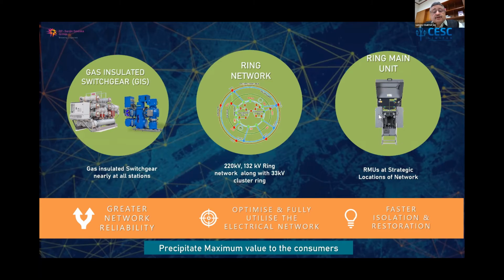We have a ring network - a 220 kV ring, a 132 kV ring, along with 33 kV cluster rings - so that any fault or disturbance in one part of the network can have loads restored to other parts very easily through our central SCADA. We also have RMUs at strategic locations of our network.